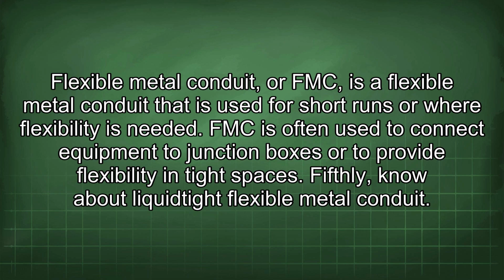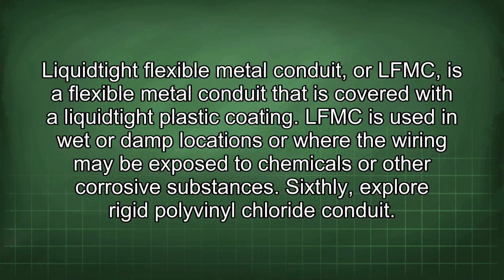Fifthly, know about liquid-tight flexible metal conduit. Liquid-tight flexible metal conduit, or LFMC, is a flexible metal conduit that is covered with a liquid-tight plastic coating. LFMC is used in wet or damp locations or where the wiring may be exposed to chemicals or other corrosive substances.